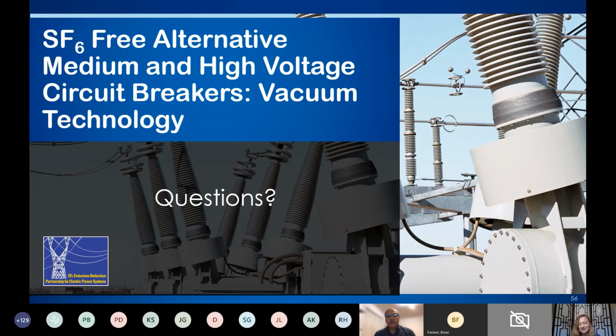Maybe I can take a stab at that to start with. This is Linus with PG&E. Really what we found is communication. There's a cost factor to consider, but communicating that it's a safer solution helps. You don't have the SF6 byproduct risk, and with a vacuum break as opposed to a pressurized vessel, you have a reduced risk of other types of explosive failure. You do have pressure on the dry air side, but those are some reasons it makes good sense in the long run to move away from it. And the maintenance costs go down, and you add in the climate risk and the persistence of SF6 in the environment. Those factors together make a good case for moving away from SF6 into an alternative.